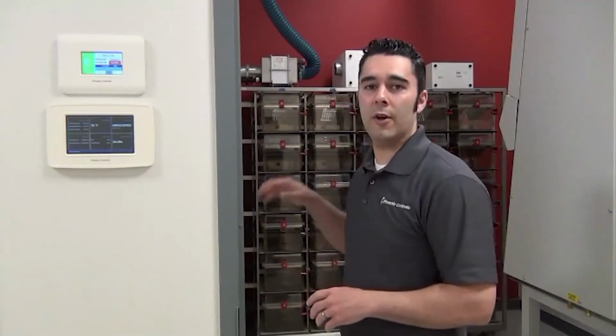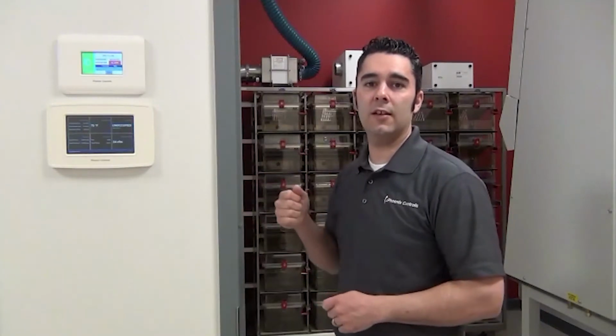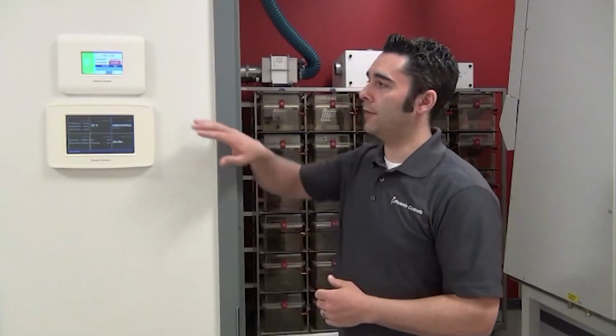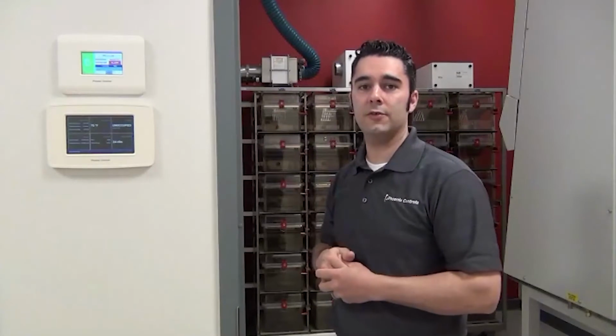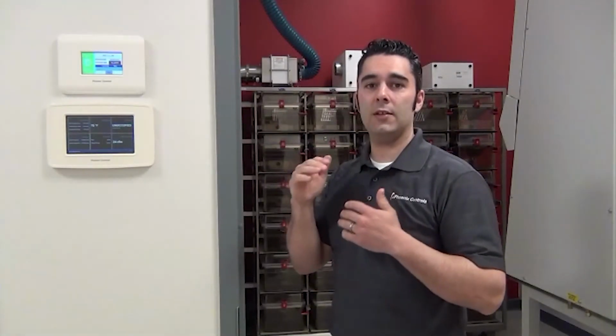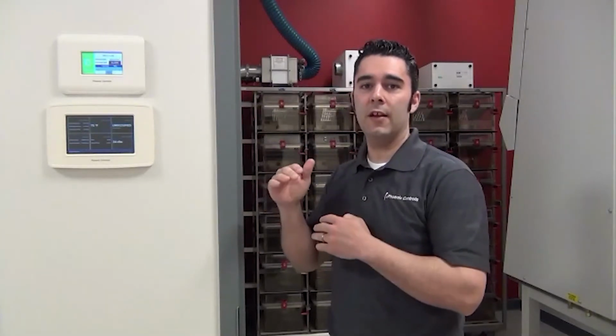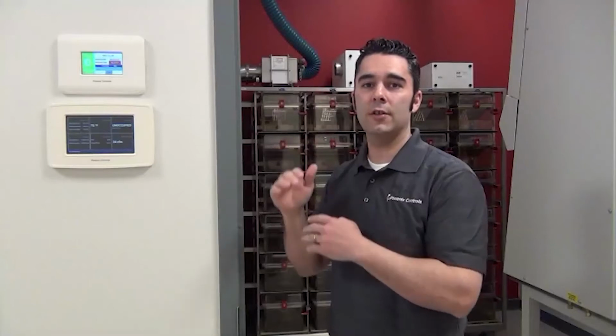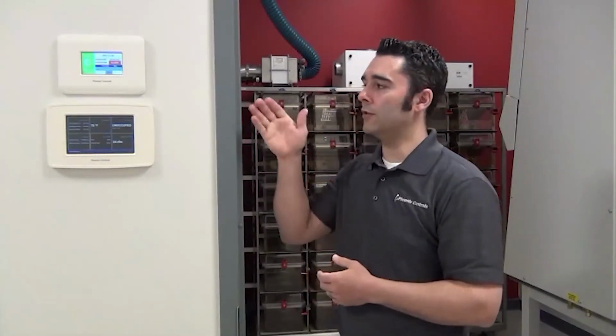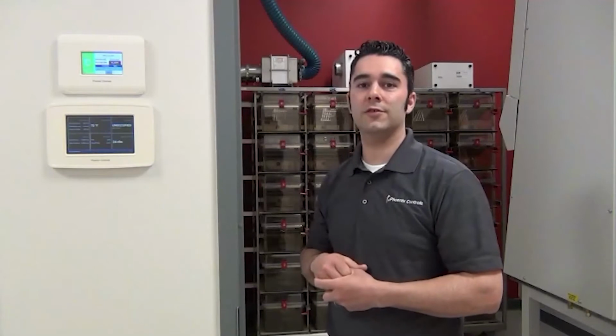So when the door is closed, no matter what's happening inside the space, if I'm taking that cage rack in and out, plugging up the airflow for that, or if I'm turning my biosafety cabinet on and off, I need to make sure that I always have negative pressure going into this room. So the advanced pressure monitor will read the differential pressure across the door. It will monitor the PID loop going in there that's controlling the volumetric offset, and it will actually vary the volumetric offset within a range to guarantee that I maintain that differential pressure. It also has alarm and trip points built into it, so if you need to alarm it to the building automation system or rewrite the differential pressure set point that the PID loop controls onto, all of that is integrated into the front end. And for this type of an environment, it works really well to guarantee the differential pressure remains constant at all times.